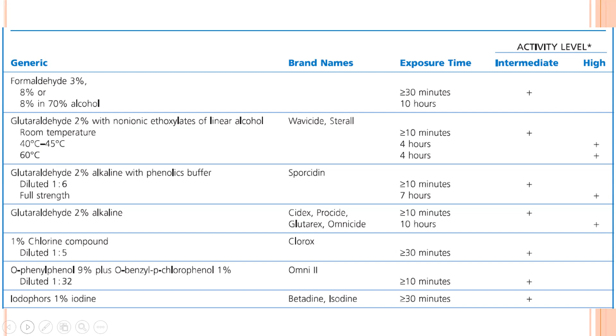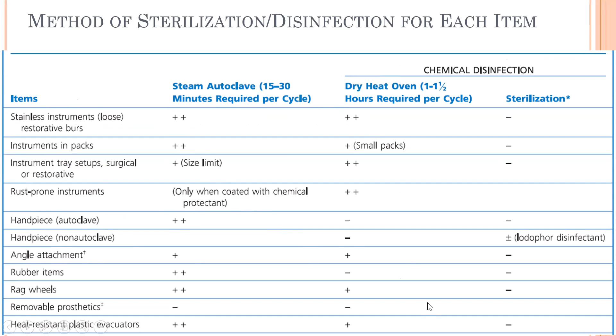So this is actually for the different instruments, what kind of sterilization is required. If you look at it, for most of the metallic instruments and those instruments which come in contact with tissues, we have to do a steam autoclave. And whenever it is susceptible to moist heat, then you can do a dry heat kind of sterilization. And if permissible, you can do a chemical disinfection.